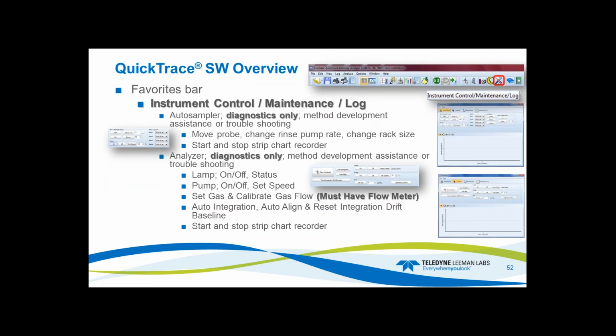Analyzer, the same thing, is diagnostics only. So you can turn the lamp off, gas off, pump off. You can calibrate the gas flow, but you've got to have a flow meter that's calibrated to carrier gas. You can reset the auto integration, so that's after you clean the cells, you reset the drift baseline, and here you can also stop and start the strip chart recorder.